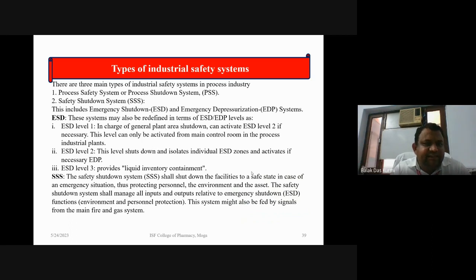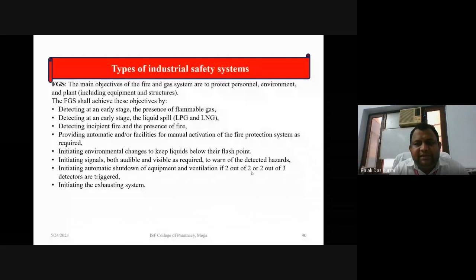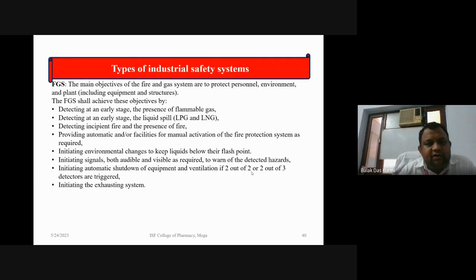So FGS, the main objectives of the fire and gas system are to protect personnel, environment, and plants, including equipment and infrastructure. The FGS shall achieve these objectives by detecting at an early stage the presence of flammable gas, detecting at an early stage liquid spills and the emergence of fire, providing automatic or facility for manual activation of the fire protection system as required, initiating environmental changes to keep liquids below their flash point, initiating signals both audible and visible as required to warn of the detected hazards, initiating automatic shutdown of equipment and ventilation if two out of two or two out of three detectors are triggered, or initiating the exhaust system.